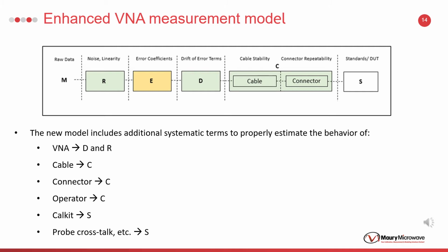VNA noise and linearity, classic error box, drift terms, cable stability, connector repeatability, calibration kit errors, and other effects such as probe crosstalk are modeled as sub-networks, and their uncertainty contributions are added to the measurement data. Let me explain each sub-network in the schematic.